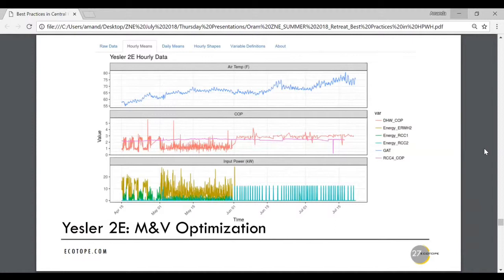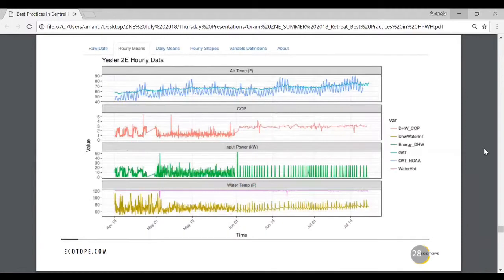Commissioning, right. We thought we had it right with the controls at the beginning, but we were firing too much resistance, and that's what this gold bar is. We got rid of all the resistance, and if you look at the COP graph, you can see we're running about a 3.3 COP on our heat pumps, on our main hot water plant, and about 2.5 on the RECIRC.